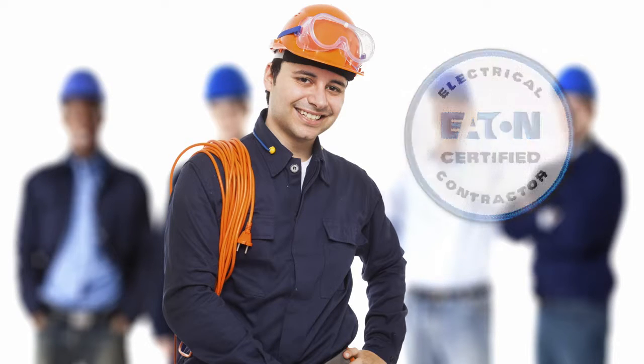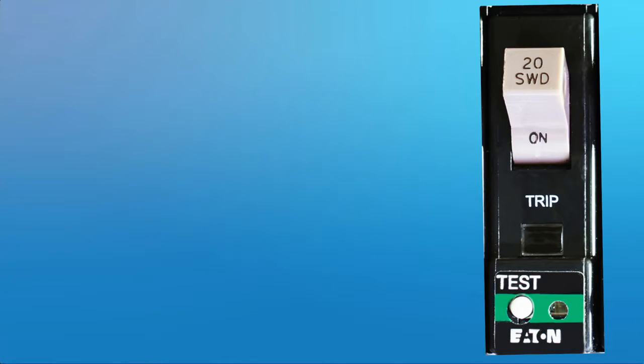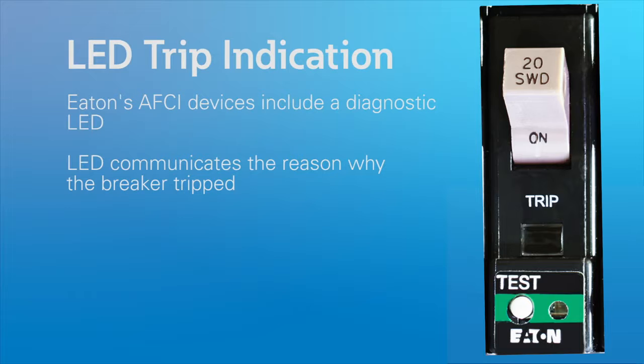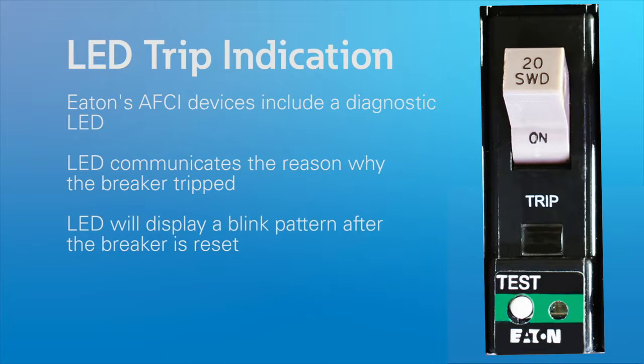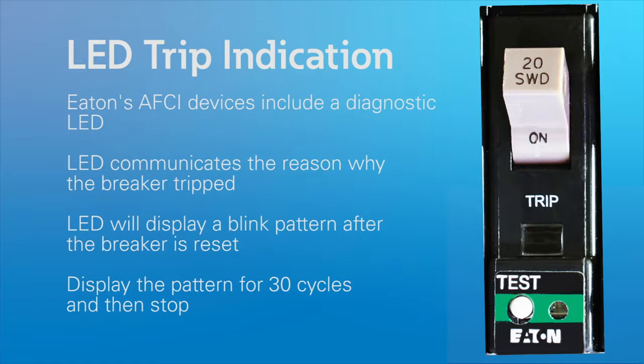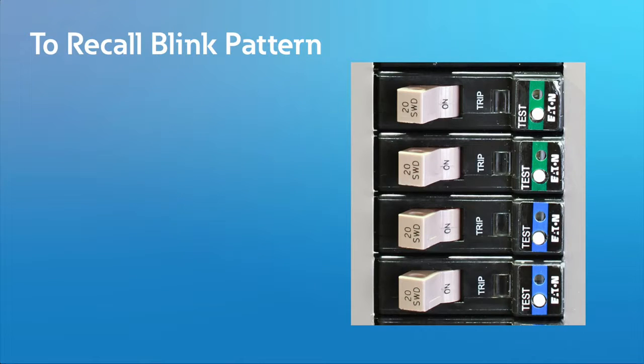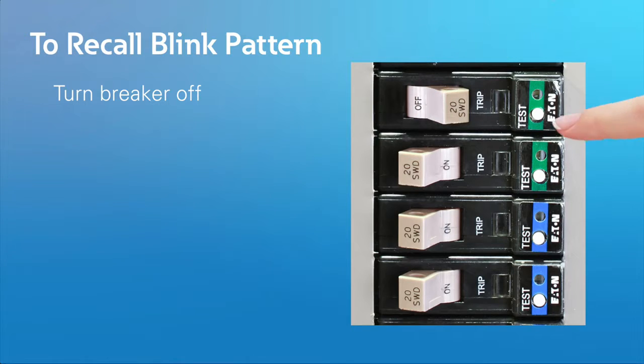Some of Eaton's AFCI devices include a diagnostic LED. This LED communicates the reason why the breaker is tripped. If the breaker trips, the LED will display a blink pattern after the breaker is reset. The LED will display the pattern for 30 cycles and then stop. To recall the blink pattern, turn the breaker off, hold the test button, then turn the breaker back on and release the test button. The breaker will recall the last trip code and display it for another 30 cycles.